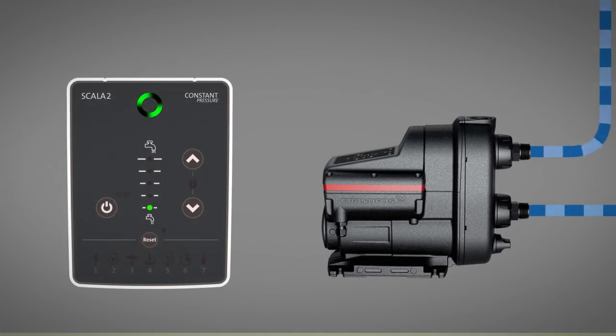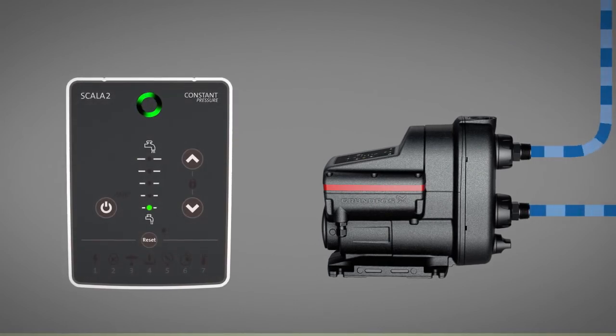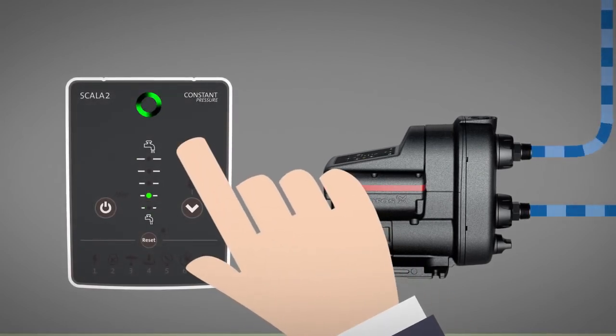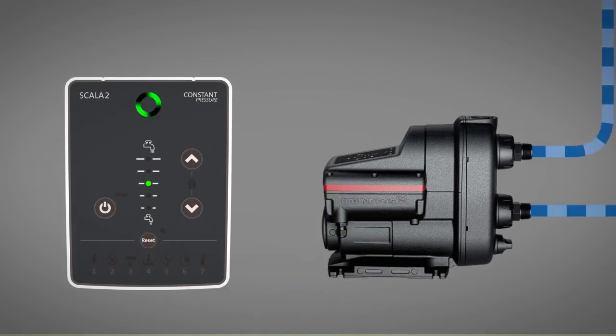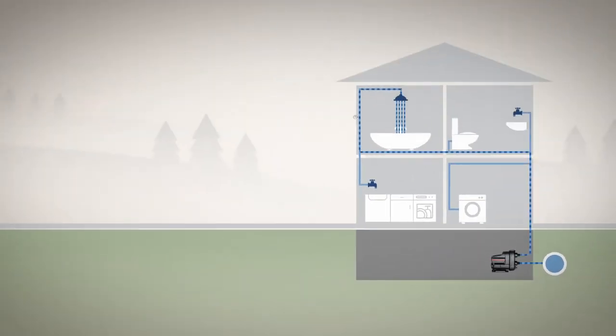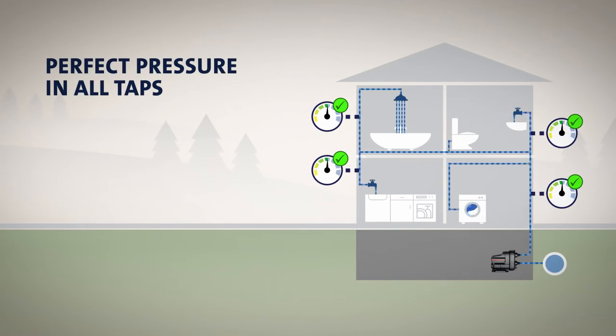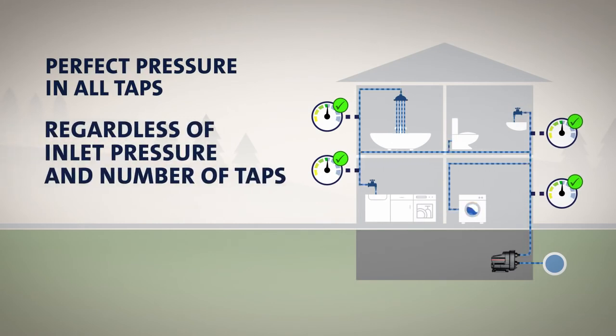For installers, this means that the setup process is quick and easy. Simply set the desired pressure level using the control panel and check the water pressure at the furthest tapping point, preferably a shower, as this is where insufficient pressure will be felt most directly by the homeowner. If the water pressure is perfect here, this will be the case at all tapping points, no matter if the inlet pressure varies or several taps are running at the same time.